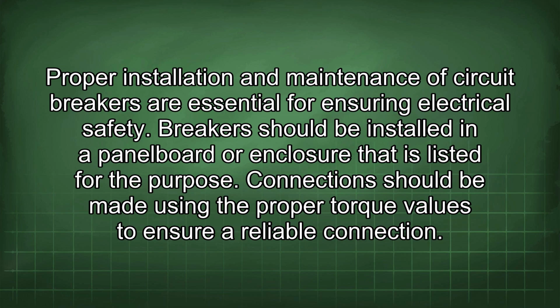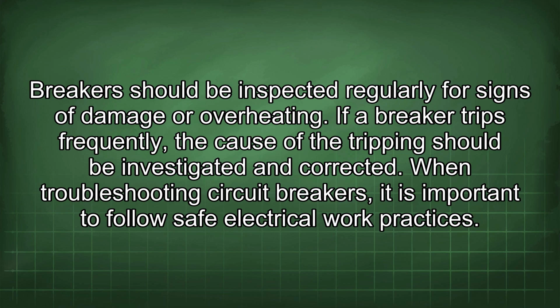Proper installation and maintenance of circuit breakers are essential for ensuring electrical safety. Breakers should be installed in a panel board or enclosure that is listed for the purpose. Connections should be made using the proper torque values to ensure a reliable connection. Breakers should be inspected regularly for signs of damage or overheating. If a breaker trips frequently, the cause of the tripping should be investigated and corrected.